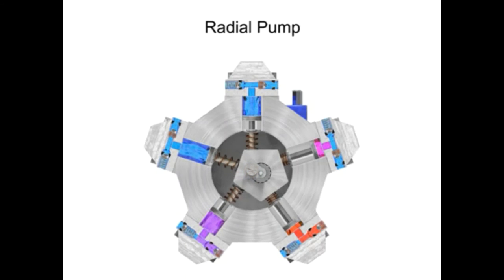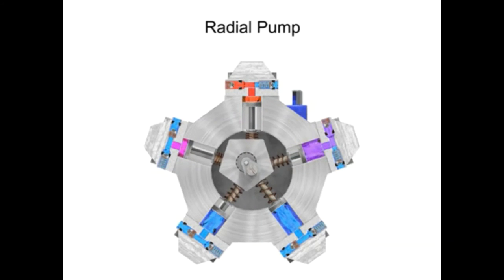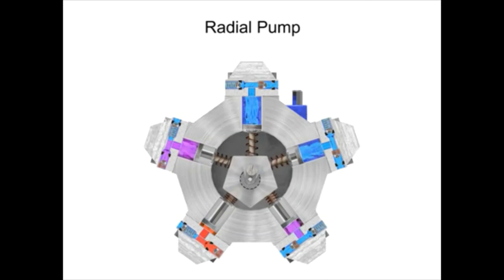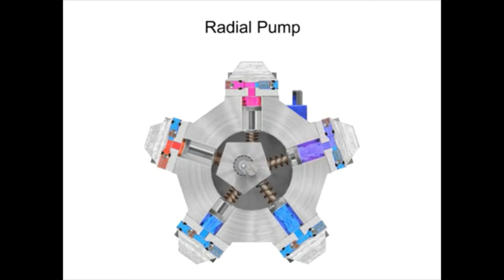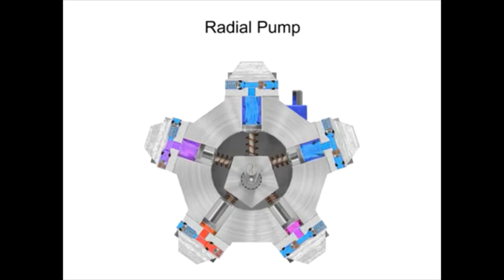As the shaft rotates, the cam moves towards the pistons, forcing them down into the cylinder block and discharging the fluid. As the cam moves away, springs help retract the piston and cause the intake stroke. Check valves ensure that fluid only enters the inlet ports and only exits the outlet ports.